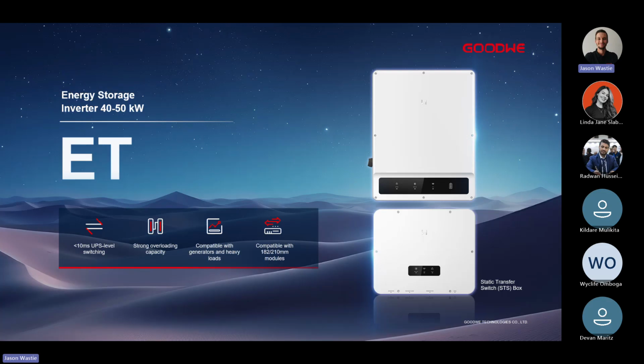Okay, so this is our three-phase high-voltage hybrid inverter. So this is our ET50. ET stands for energy storage three-phase, and the 50 kilowatt iteration of this unit is the unit that we'll be discussing today. If you look on the right-hand side of this picture, you'll see there is a hybrid inverter at the top, and underneath that, the static transfer switch.